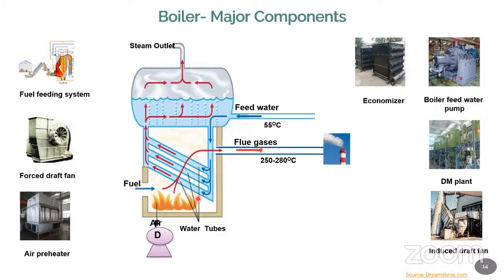When partial combustion takes place, the hydrocarbon content in the fuel will not be utilized. The energy is not completely released. Rather, it releases CO. It releases carbon. So if the fuel is not properly burned, then CO will be released. Carbon monoxide will be released. So that will again pass on to the flue gas, the chimney, and the smoke color is completely black. Okay, so the color indicates a very important point. So smoke color black is an indication of insufficient air and incomplete combustion. Okay, so that means you need to pump more air now.